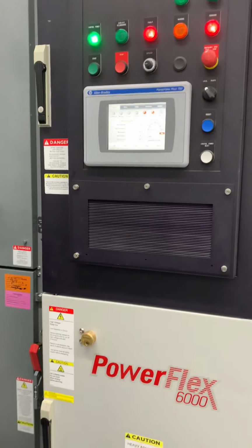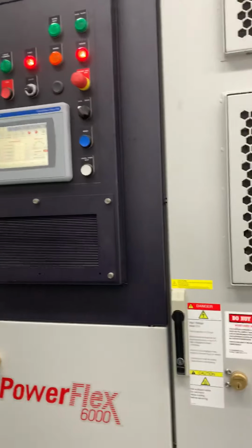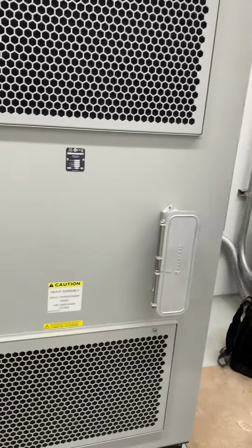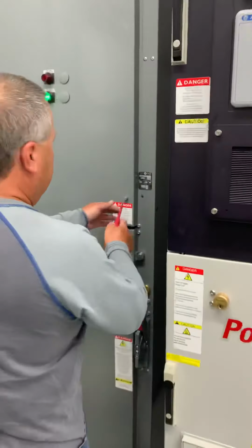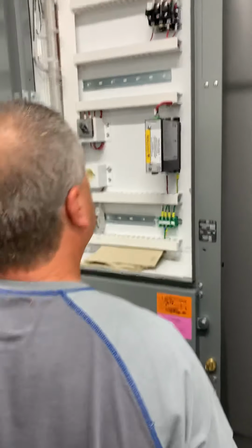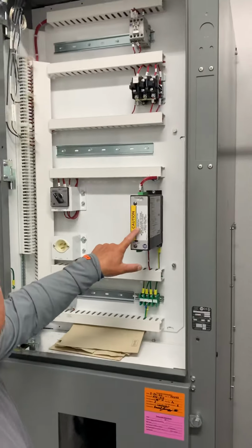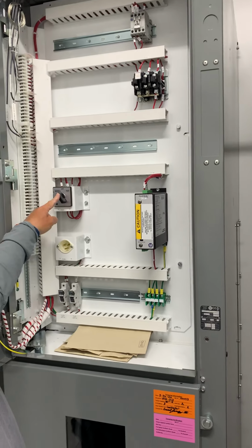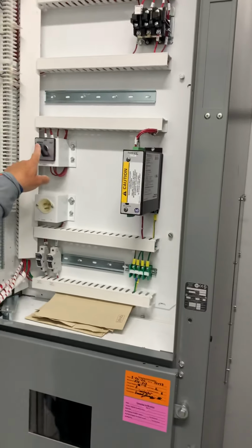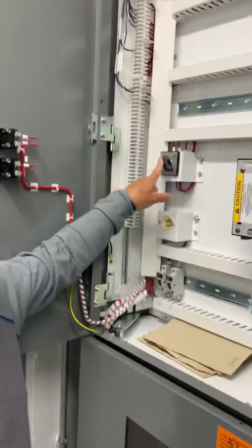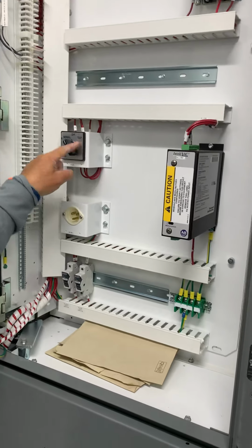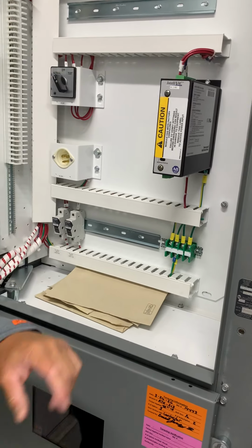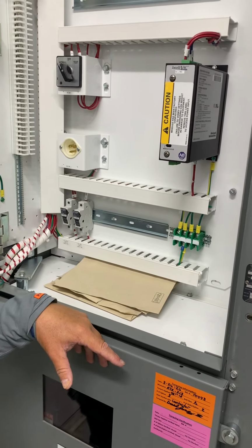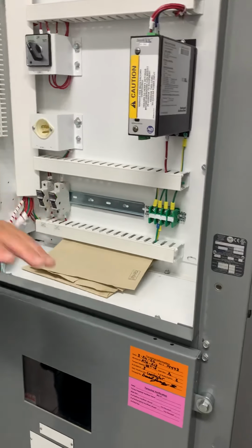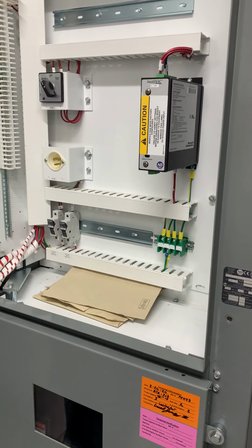Yeah. So the only thing in this cabinet, let me get my screwdriver, the only thing in this cabinet is your controls for the contactor. You've got your IntelliVac here, and if you're running and not troubleshooting, it should always be in normal. If you want to troubleshoot it without medium voltage and you have your disconnect off, then you put this over on test, plug an extension cord in here, plug it into the outlet, and that gives this remote power to operate it in test mode without medium voltage on it.